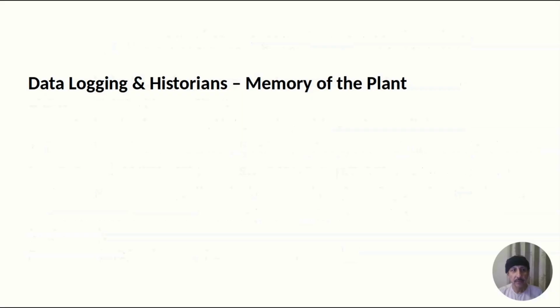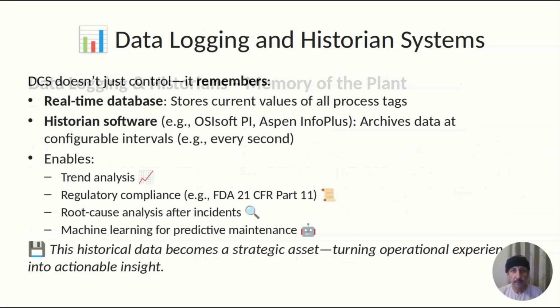Data logging and historians, the memory of the plant. A DCS doesn't just control, it learns. Every sensor reading, every valve position, every alarm is timestamped and stored in a historian, a specialized time series database optimized for high-speed writes and efficient queries. This data is gold.